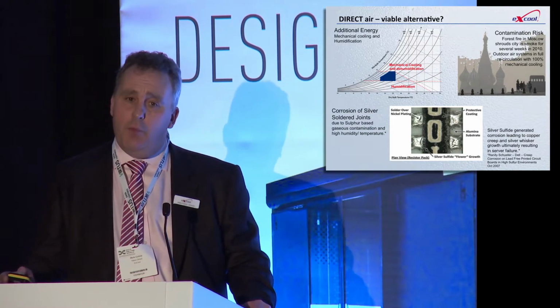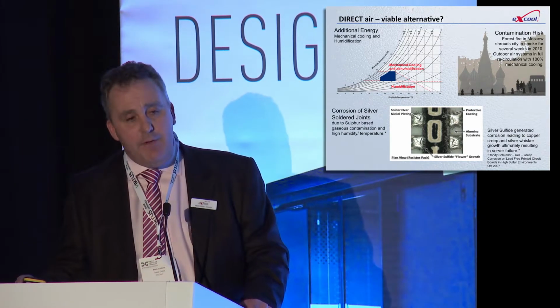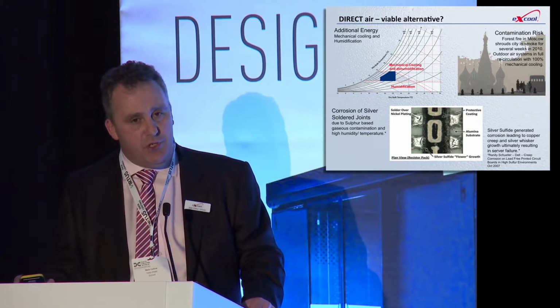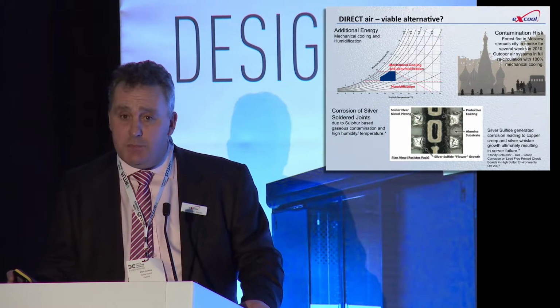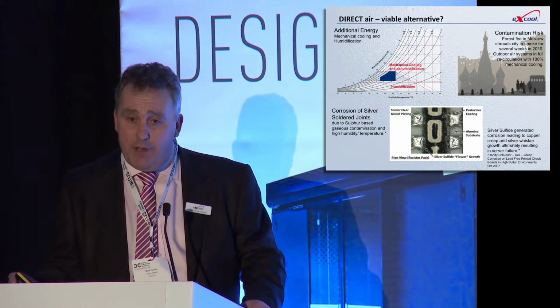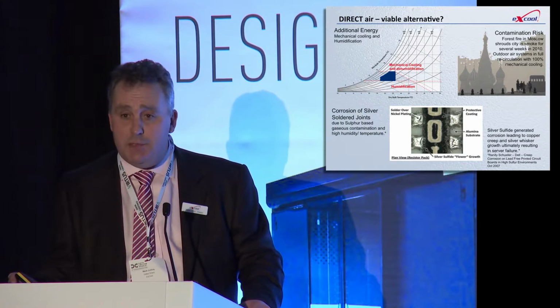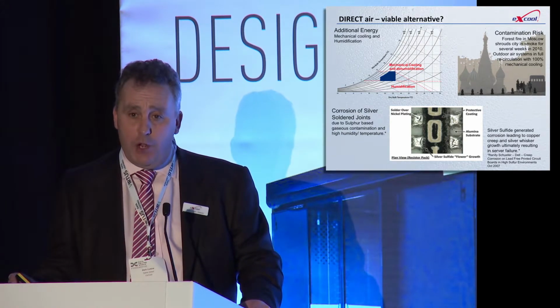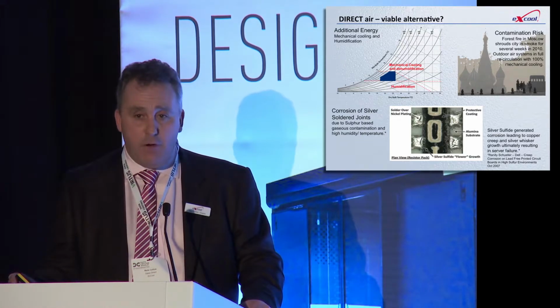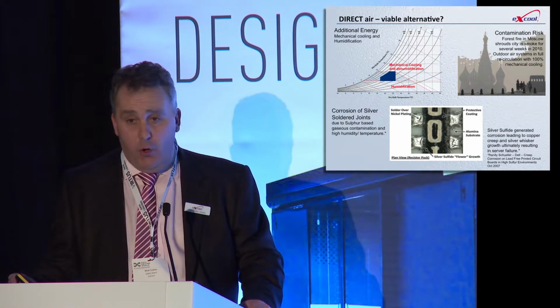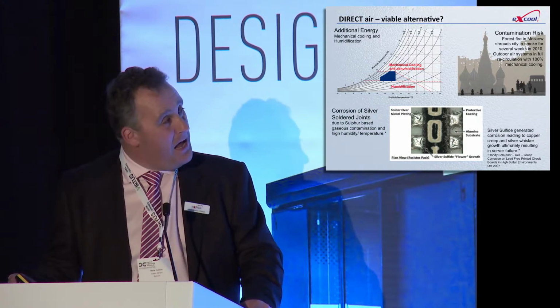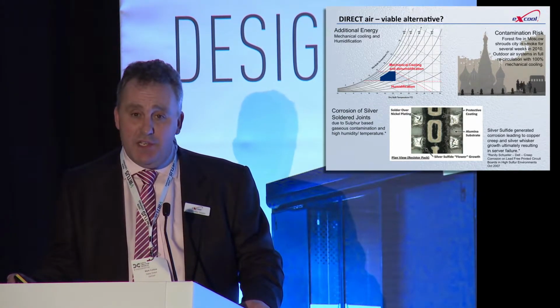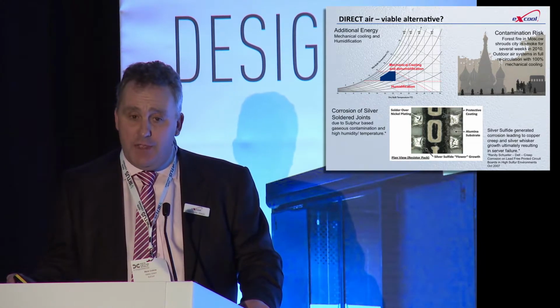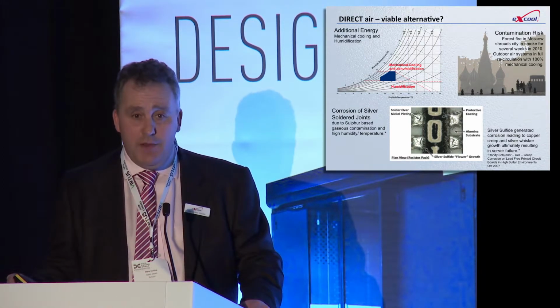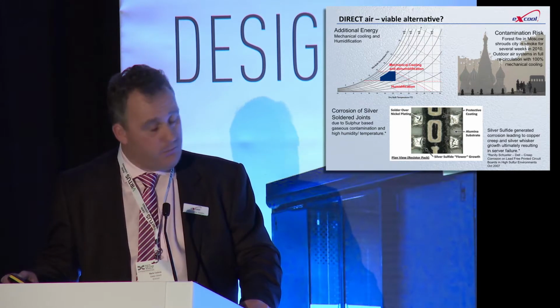One of the products that has been favoured in certain regions over chilled water and has produced some really low PUEs is direct air systems. The problem our clients have with direct air systems is a contamination risk from poor air quality. A simple car fire or a forest fire or a building fire local to your site, or bonfire night in this country on the 5th of November, will produce smoke locally, which will be taken into the data centre. Therefore, you need to shut the outdoor air down and recirculate all of your air within that space, therefore needing full compressor backup to maintain conditions.